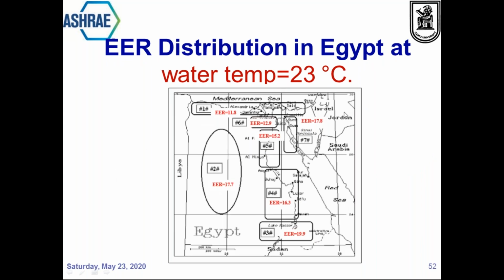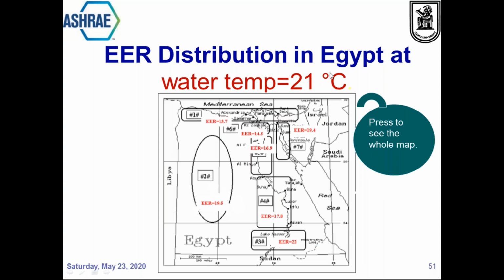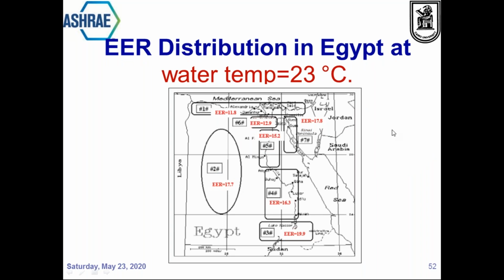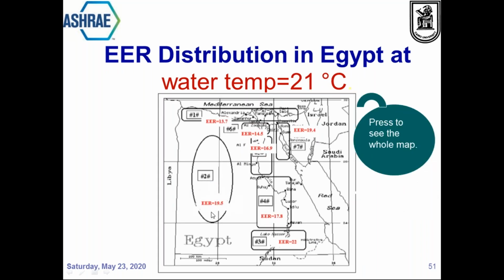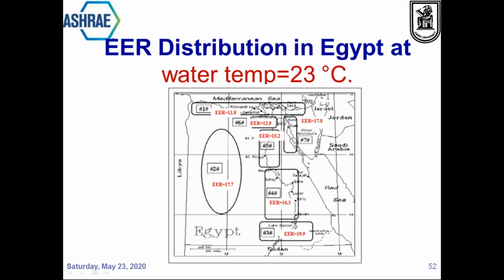If we use water temperature of 23, we expect to have less energy efficiency. Why? Because the water we spray is at a little bit higher temperature, while in the previous one, the water we sprayed was at 21 degrees centigrade. So naturally, in this case, we have higher energy efficiency ratio, while in here, the energy efficiency ratio is reduced. For example, here at 21, the energy efficiency ratio is 19.5. Fine, very good. But if we go to 23 degrees centigrade water spray temperature, then the EER is 17.7, still higher than the conventional value.